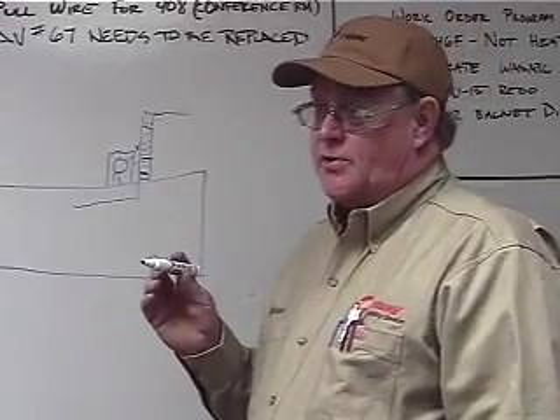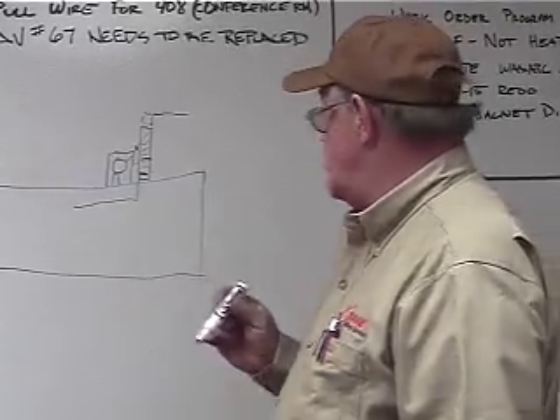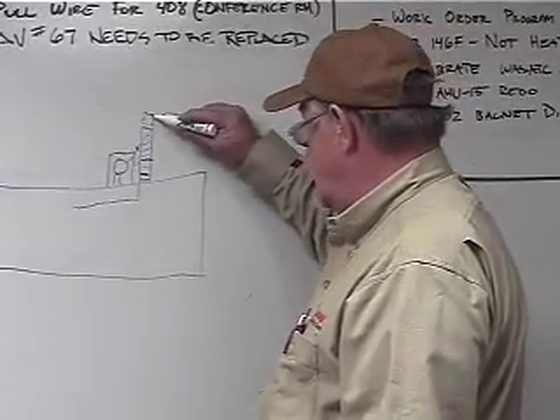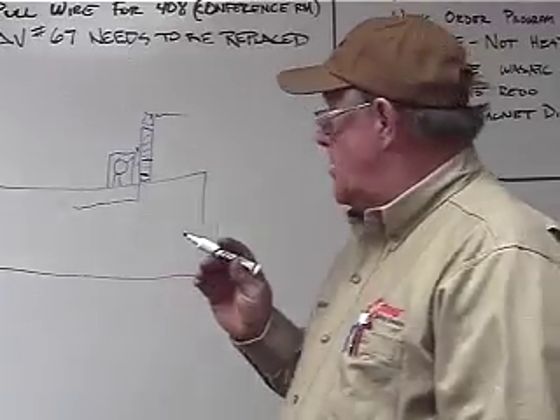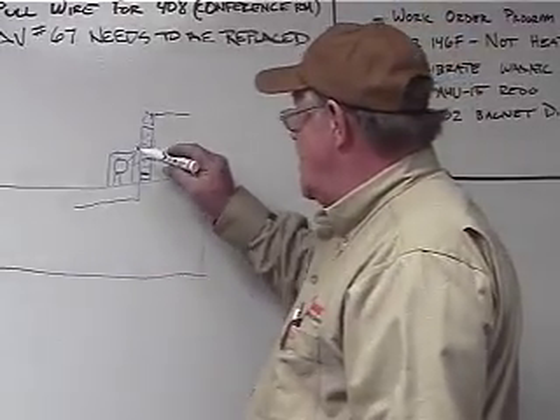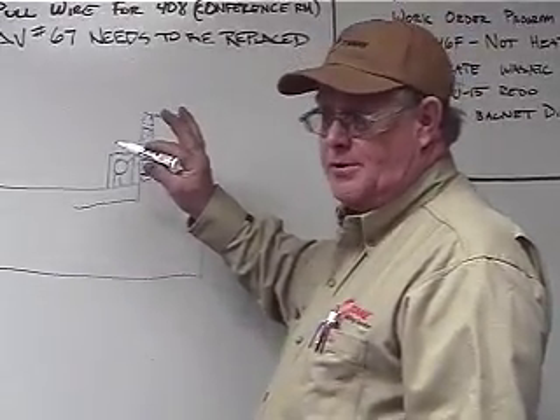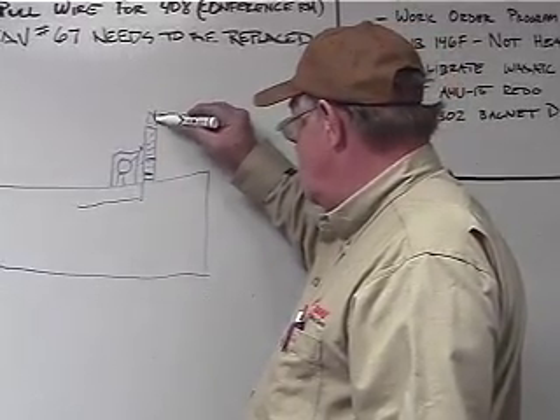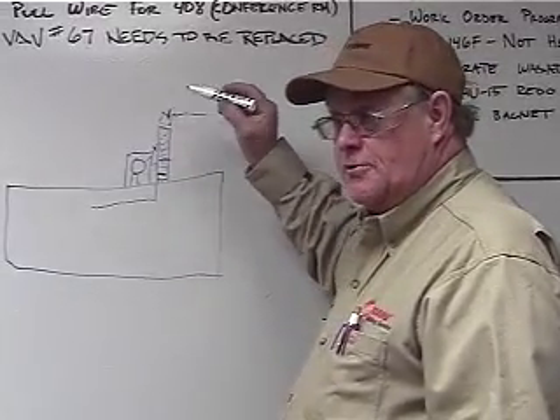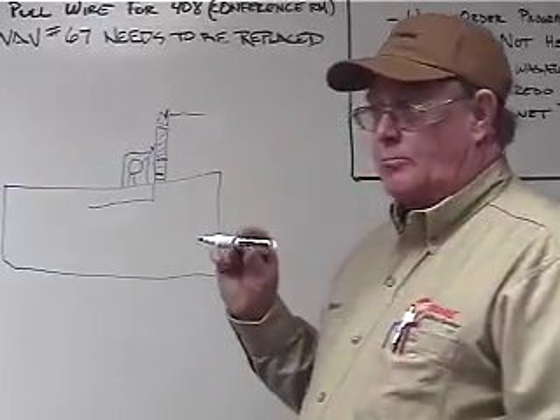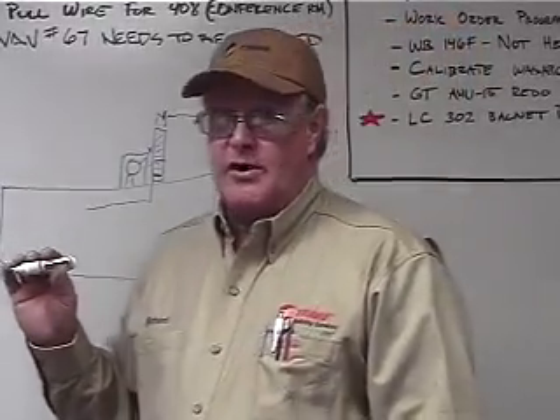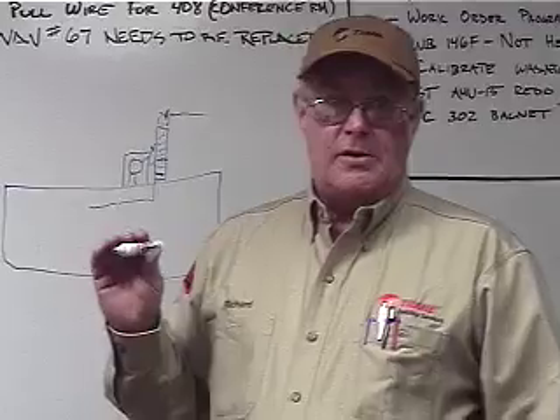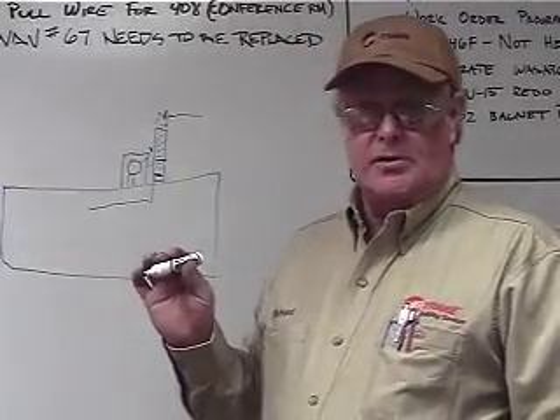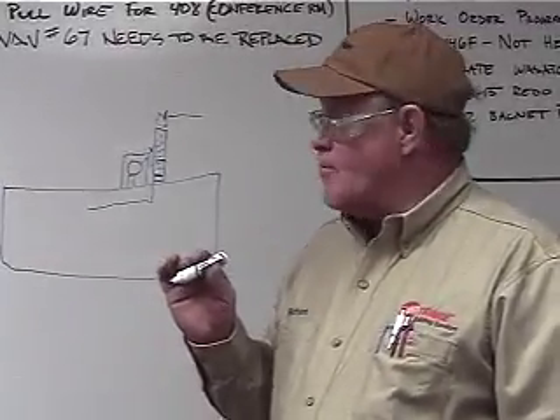When it hits 22 degrees Fahrenheit, it shuts off that little pump that's up here. So if you see this fan running all the time, don't get alarmed. But if this little purge pump up here is continuously running, we're getting purge time on it. In other words, we've got a lot of non-condensables in it, which means that we need to start looking at doing a leak check.